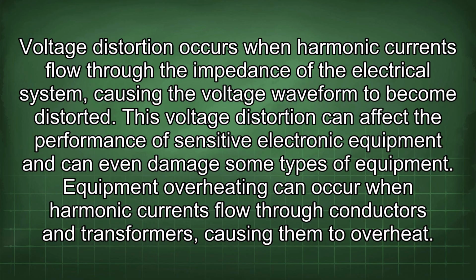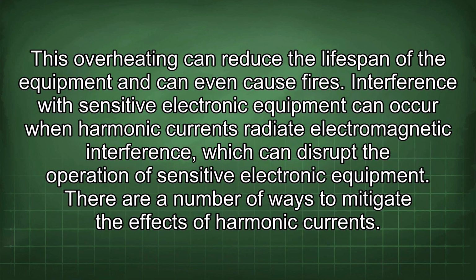Voltage distortion occurs when harmonic currents flow through the impedance of the electrical system, causing the voltage waveform to become distorted. This voltage distortion can affect the performance of sensitive electronic equipment and can even damage some types of equipment. Equipment overheating can occur when harmonic currents flow through conductors and transformers, causing them to overheat. This overheating can reduce the lifespan of the equipment and can even cause fires. Interference with sensitive electronic equipment can occur when harmonic currents radiate electromagnetic interference, which can disrupt the operation of sensitive electronic equipment.